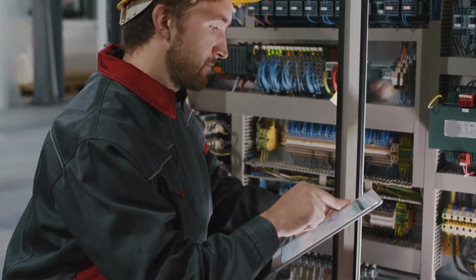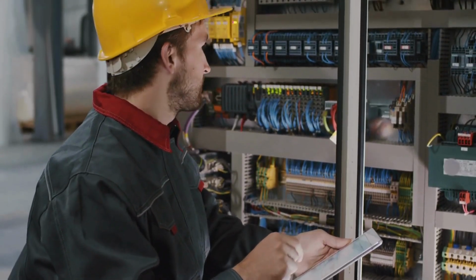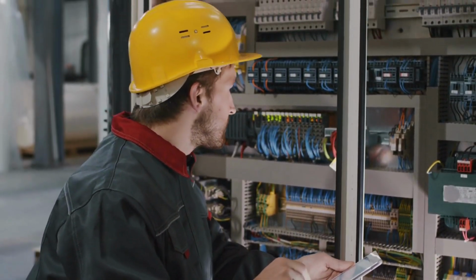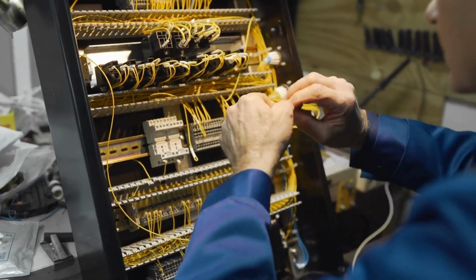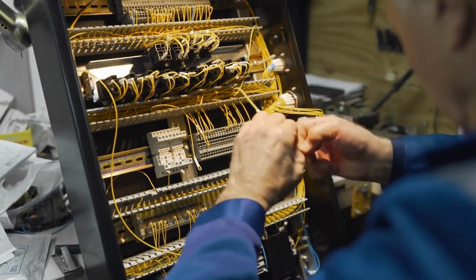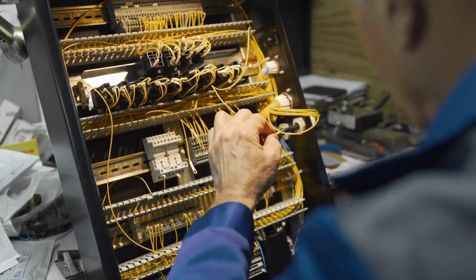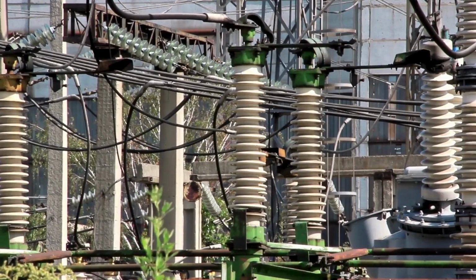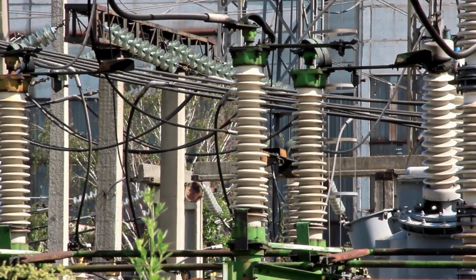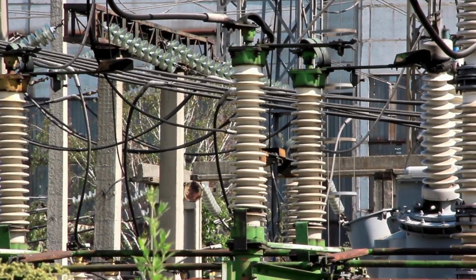Yes, this feels like wasted time when you're trying to get work done, but it's not wasted if it keeps you alive. For equipment without specified discharge times, or when you're not sure what's inside, 15 minutes is a reasonable minimum. For large industrial drives or power factor correction banks, you might need to wait even longer.